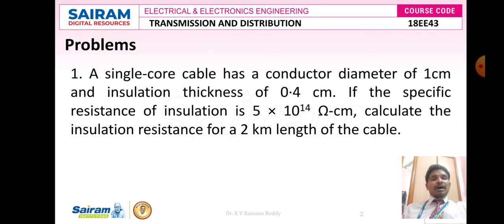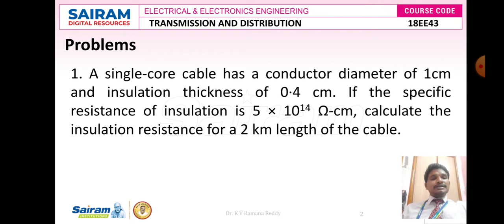Problem number one: a single core cable has a conductor diameter of 1 centimeter and insulation thickness of 0.4 centimeter. If the specific resistance of insulation is 5 × 10^14 ohm-centimeter, calculate the insulation resistance for a 2 kilometers length of the cable.